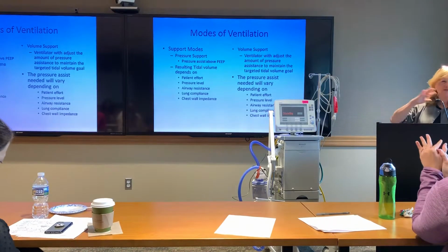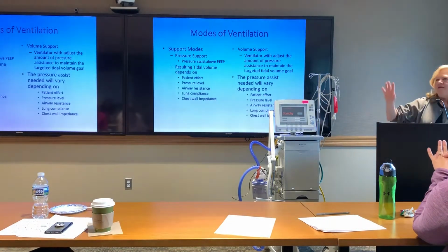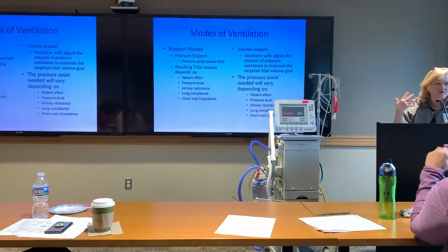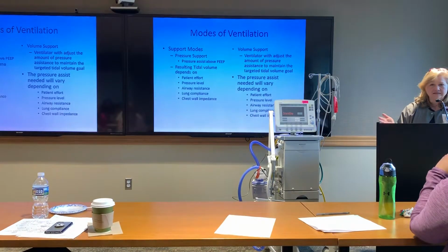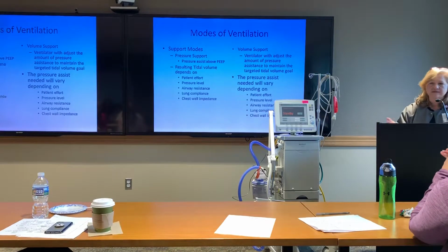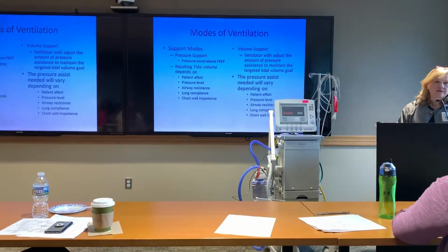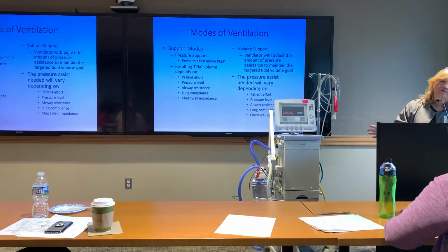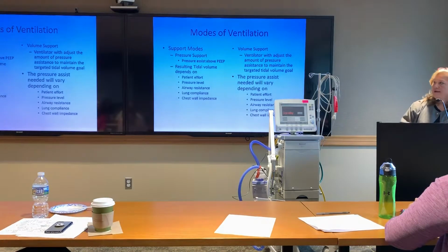All right, so assist control mode. That's a great mode. There's a mode on here called SIMV, which I'm not going to bother to talk about. I don't think you guys use it in neuroscience. The only place it really has a role is in PACU, post-op, if somebody's recovering from anesthesia. You would put it on there and give them some pressure support, and when they start breathing regularly on their own, you take the SIMV off, and you just leave them on pressure support. It was the way we ventilated people for the longest time because we didn't have a lot of choices before.